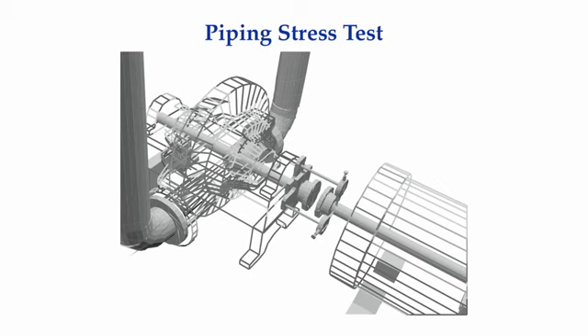Static piping stress is defined as the amount of stress induced into the machinery when it's not running. Dynamic piping stress is defined as the amount of stress induced in the machinery when it is running. Bear in mind that some of our machinery is flowing hot process fluids. Metal expands when it gets hot and may therefore move enough to induce loads when the equipment is operating.